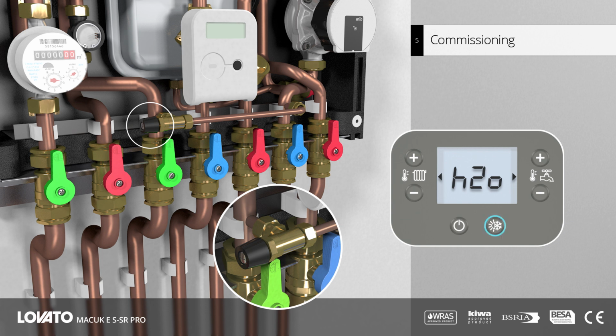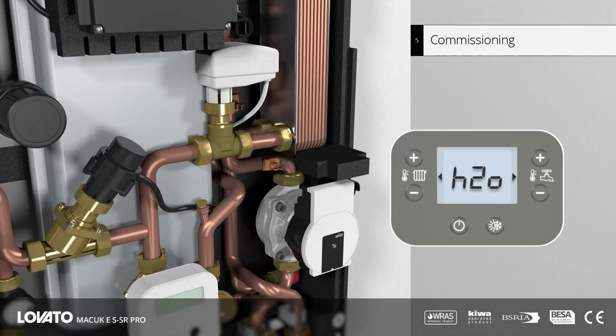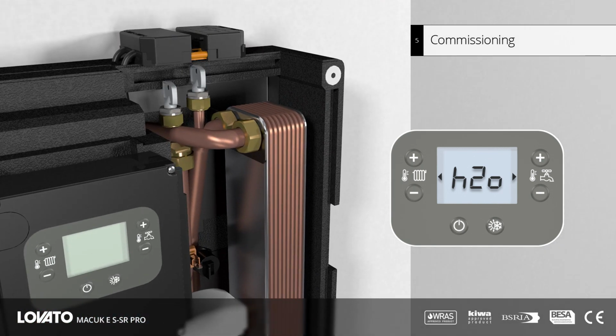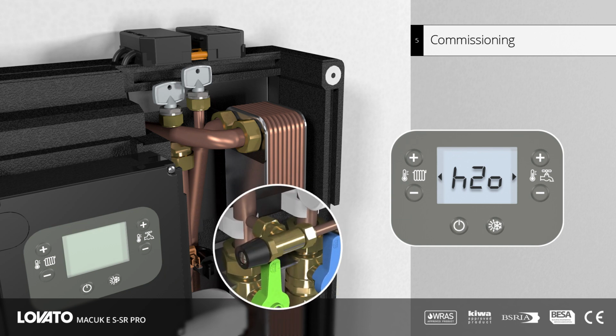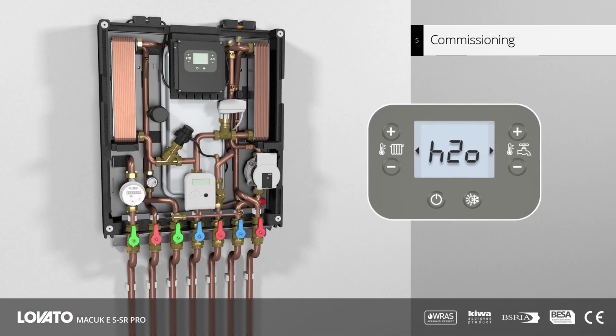Press the summer-winter button and the circulation pump will start to run. Lastly, use the manual air vents to bleed all pipework of excess air before closing the filling loop valve. Press the power button to exit the heating circuit pressure mode.